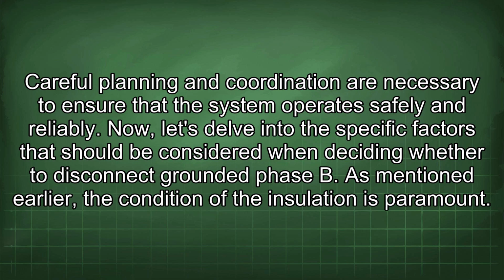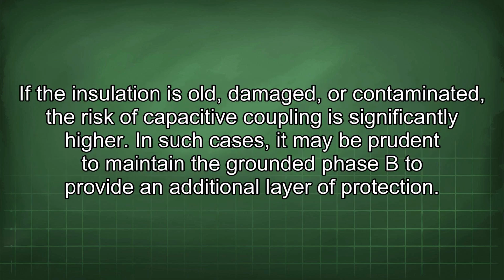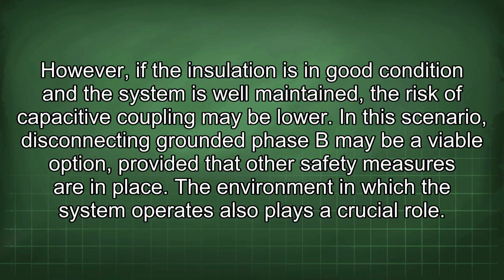Now, let's delve into the specific factors that should be considered when deciding whether to disconnect grounded phase B. As mentioned earlier, the condition of the insulation is paramount. If the insulation is old, damaged, or contaminated, the risk of capacitive coupling is significantly higher. In such cases, it may be prudent to maintain the grounded phase B to provide an additional layer of protection. However, if the insulation is in good condition and the system is well maintained, the risk of capacitive coupling may be lower. In this scenario, disconnecting grounded phase B may be a viable option, provided that other safety measures are in place.